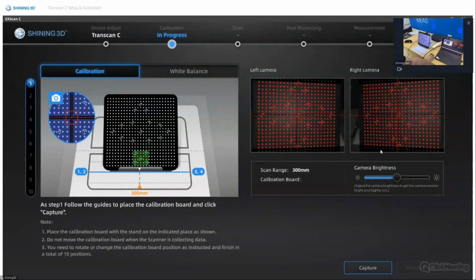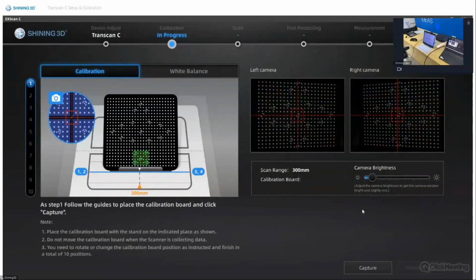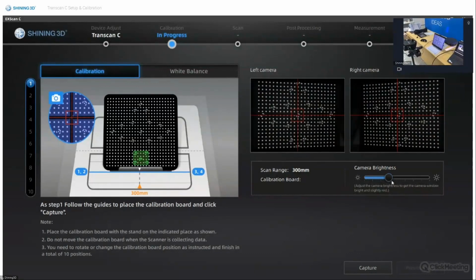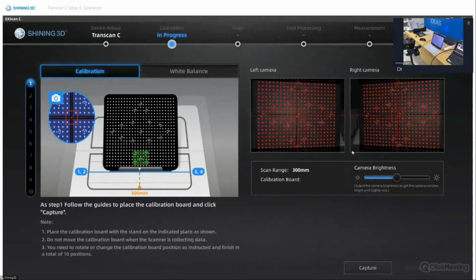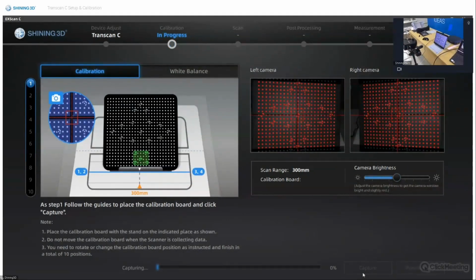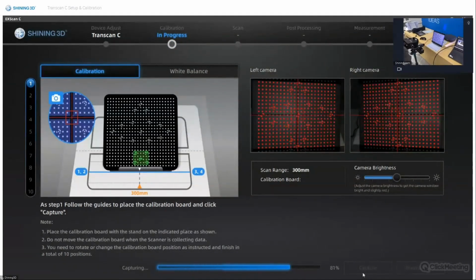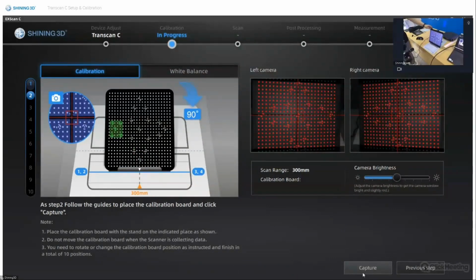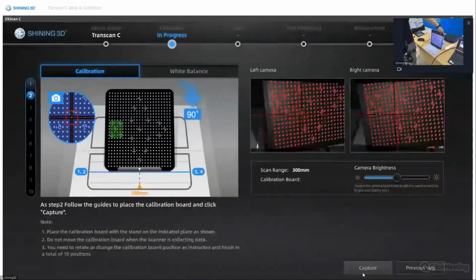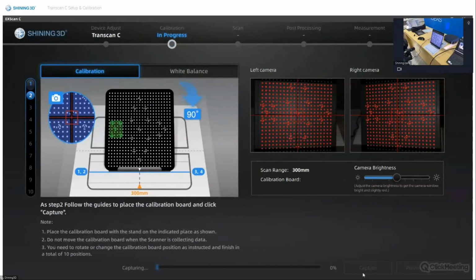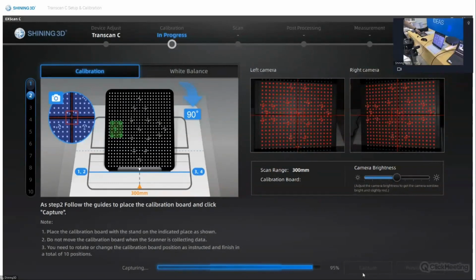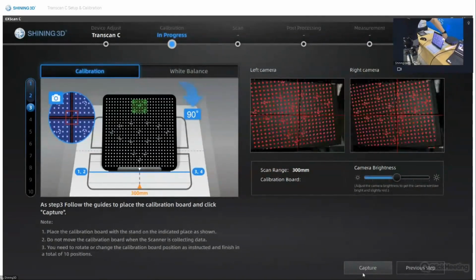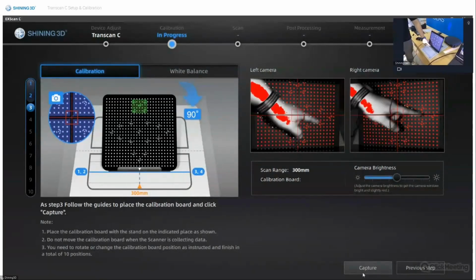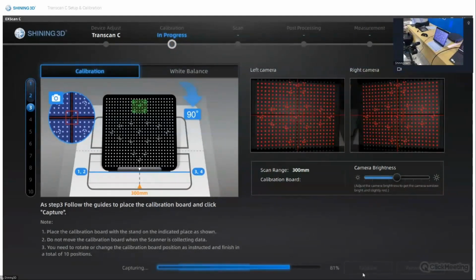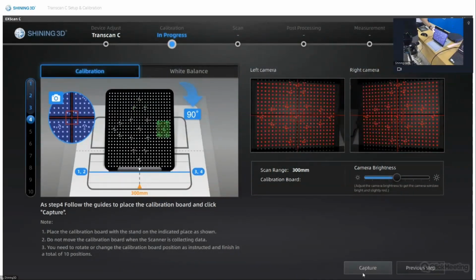Then the other one is the camera brightness. I usually go from the lowest brightness setting, and I go up. You need to stop at the first step where you see red on the calibration board. This means you're at a good brightness. And then you can click on capture, or you can hit the space bar. Usually if the distance is not changed, you don't need to change the brightness again. So for step 2, you just turn it 90 degrees. And step 3, also make sure the center line aligns. Step 4.